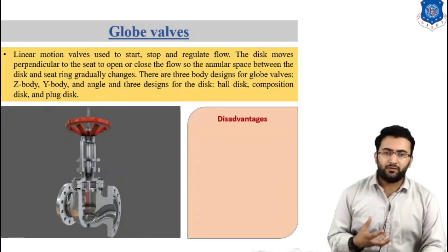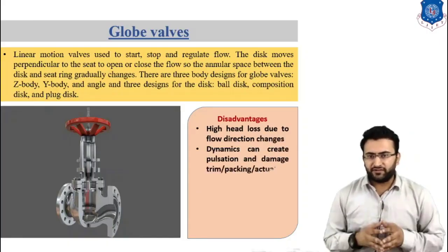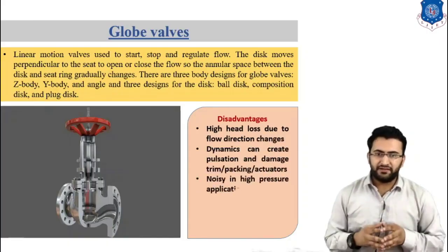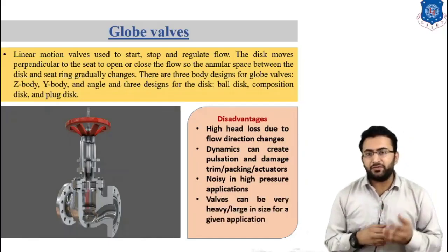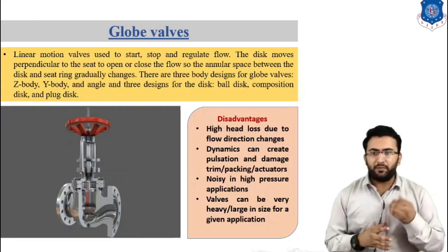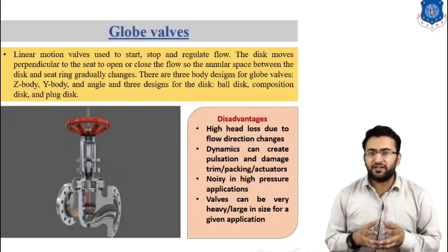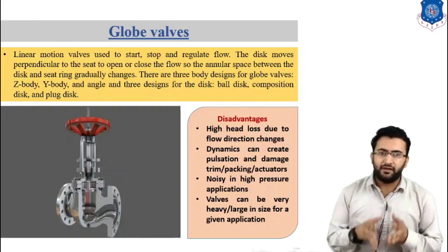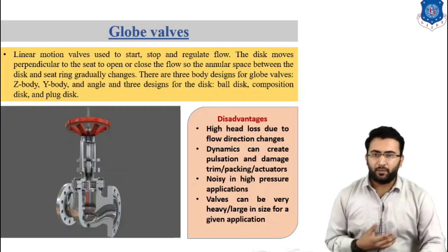Now let's talk about disadvantages of globe valve. Globe valve has high head loss due to the flow direction change. Dynamic forces can create pulsation and damage packing and actuator, and it's noisy in high pressure applications. Valve can be heavy and large in size for a given application compared to other types of valve. So this is all about globe valve.